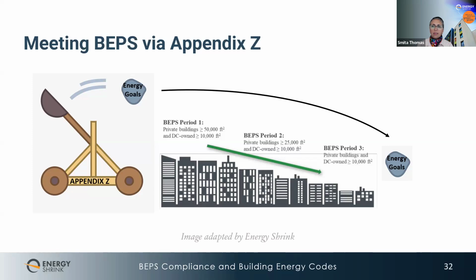One thing Appendix Z does not yet have, and we might start seeing in coming years, is consideration of emissions from refrigerants. Refrigerants have extremely high emissions. The typical R410A used in our HVAC systems has a global warming potential—roughly 2,000 times greater than carbon dioxide, using round numbers.